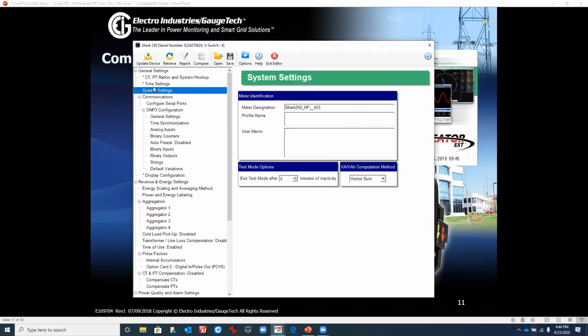So we'll go to the system settings next, and in that area you can set up the meter designation. You assign a meter name, and this meter name would be anything, if it's a unique situation. You want to specify what that designation name is. By the way, if you're a utility and using MV90, that name would be your device ID name in MV90. And then there's also an area for scratchpad work where you can write in some notes, anything you want the meter to display when you first connect to it.